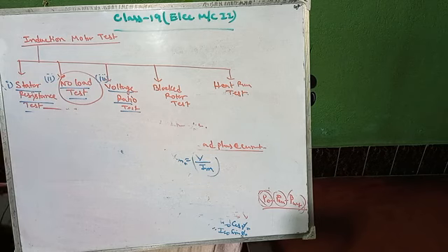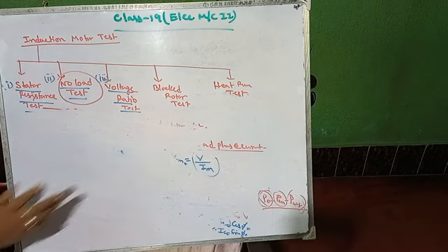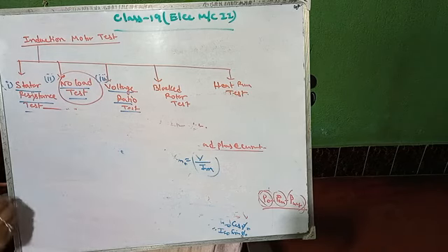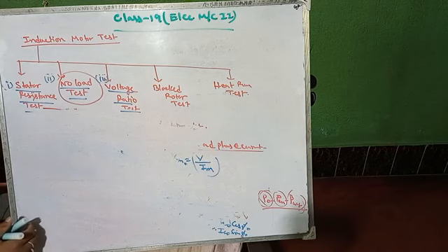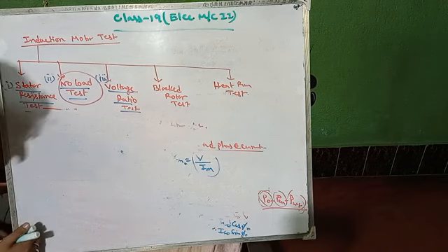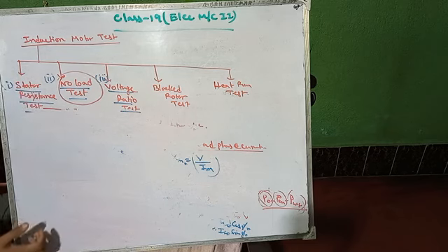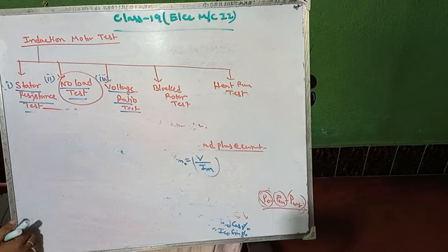For this test, the rotor is kept open and made to stand still, that is, no rotation takes place. Then the voltage that appears across the rotor conductor will be measured by the voltmeter, and the voltage ratio can be found.